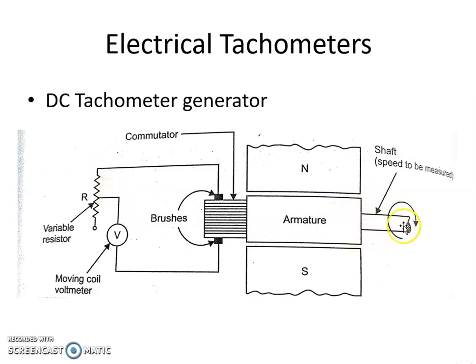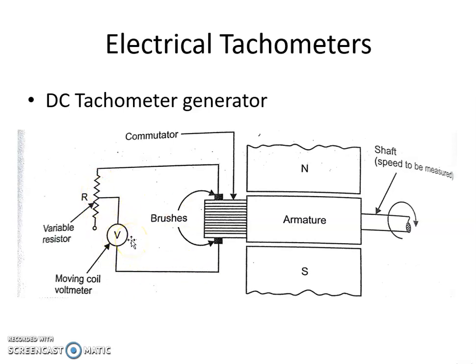Whenever the armature rotates, it induces voltage across the brushes, which is measured by the voltmeter. As the angular velocity increases, the voltage or EMF developed also increases. Therefore, the EMF induced is directly proportional to the angular velocity. A variable resistor is used to limit the flow of current to the voltmeter. In this way, the angular speed can be measured by means of a DC tachometer generator.